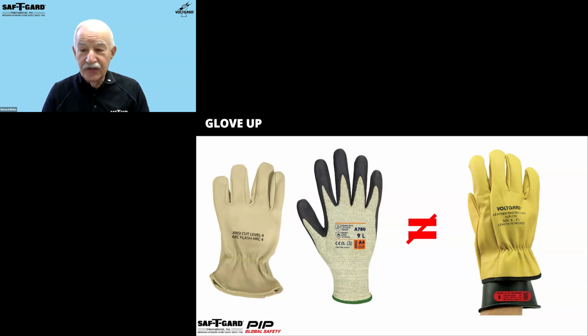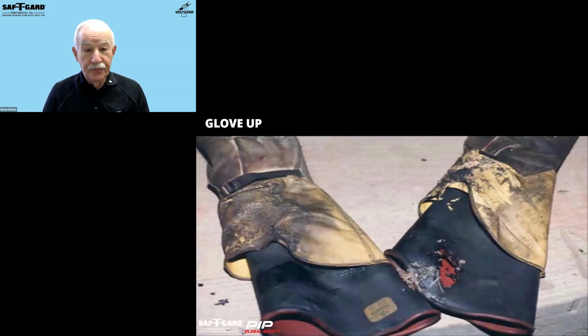There is a very, very slim perimeter where there's no shock hazard, but there might be some arc flash or arc blast. But as I said, in over 90-plus percent of the cases, 100% of the cases, that arc is coming from an electrical incident, so that shock hazard is there. ARC-rated work gloves offer no shock protection. Rubber insulating gloves are an essential element in protecting workers that are exposed to high voltage currents. Shock protection is that primary benefit. And today, the rubber insulating gloves and the leather protectors that go with them provide that arc rating as well as the shock protection. Rubber insulating gloves provide significant burn protection as well in the event of an arc flash. So you've got really many layers of protection against that arc flash as well as the shock hazard.